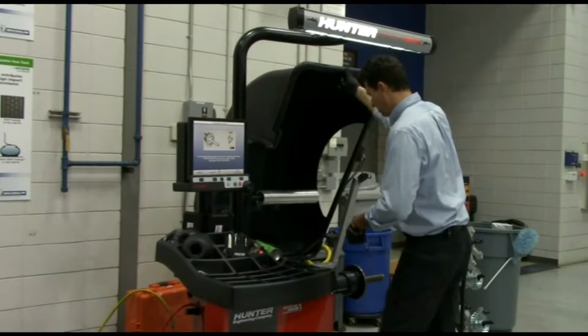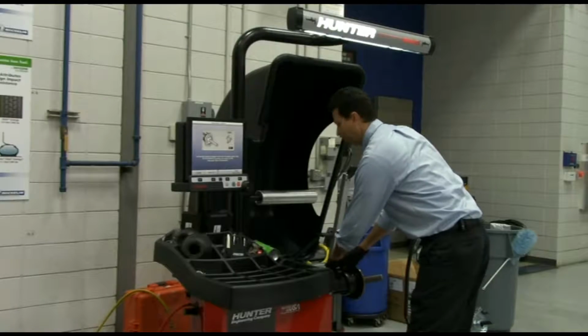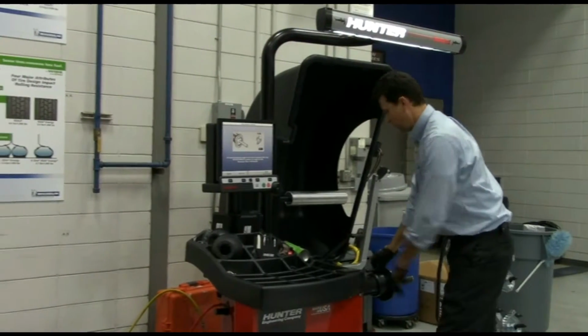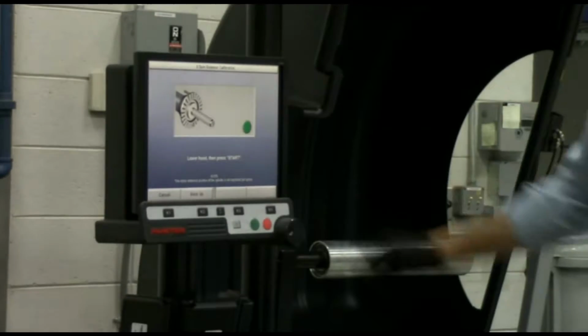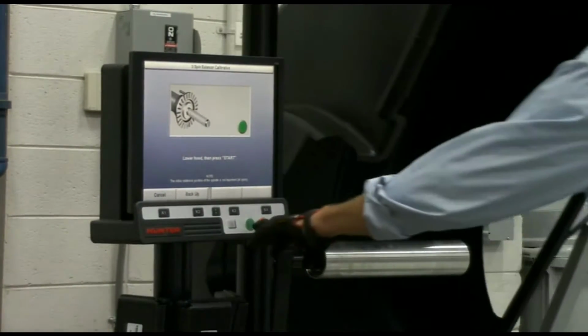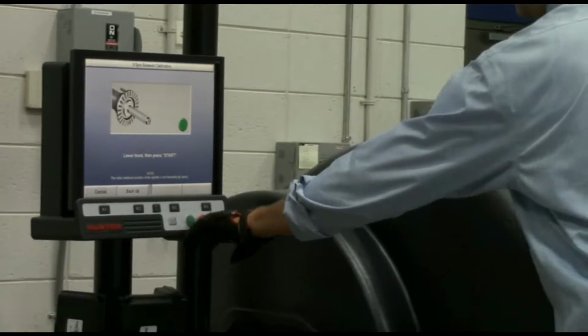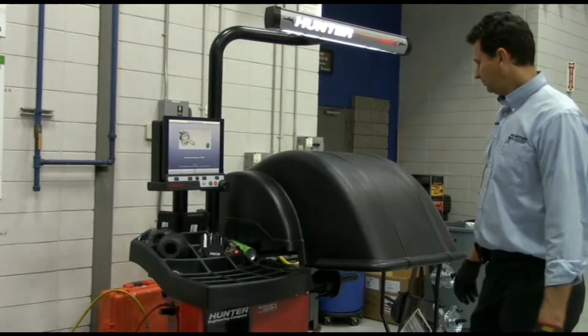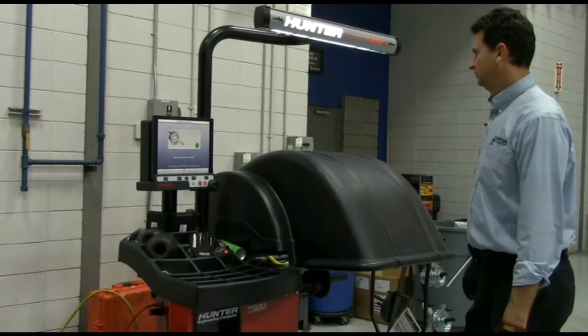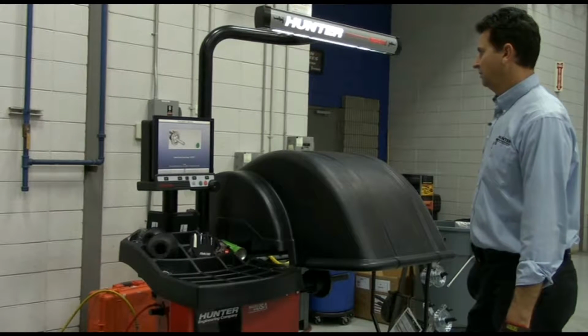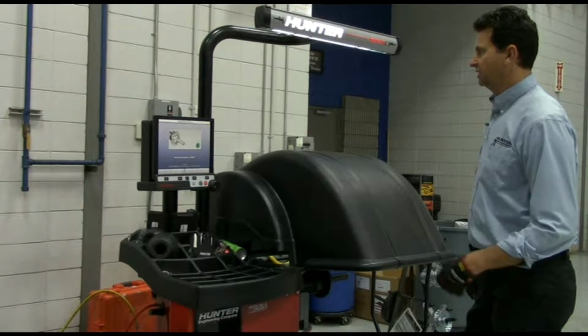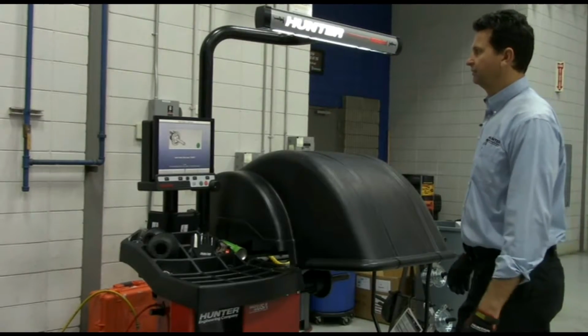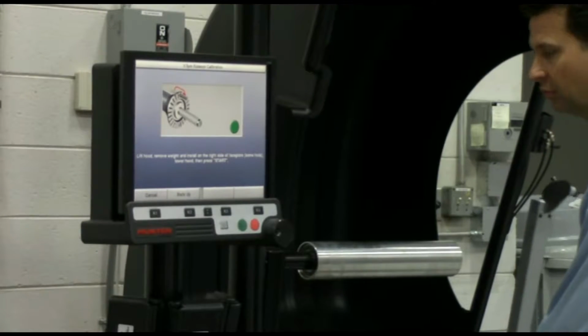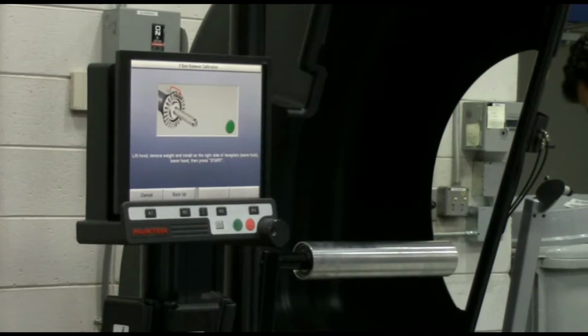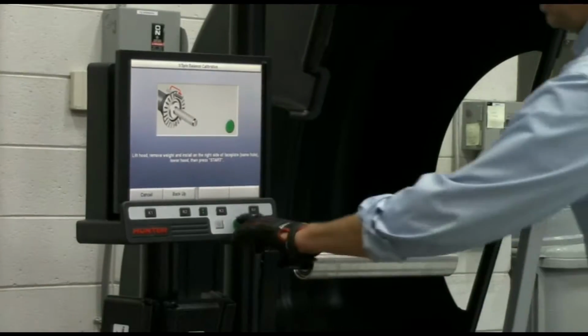So I raise the hood. It tells me to place the cal weight on the left-hand side of the hub and index it to 12 o'clock where my hammerhead laser comes on, and I press K4 for enter 12 o'clock position, and then I lower the hood and press start. It'll spin about 10-15 seconds, and then it's going to tell me to move the weight to the other side. So I move the weight to the outside of the hub. Same thing, lower the hood, press start.